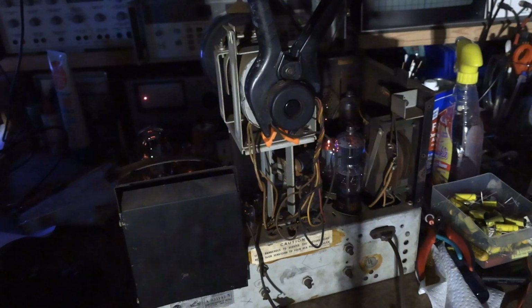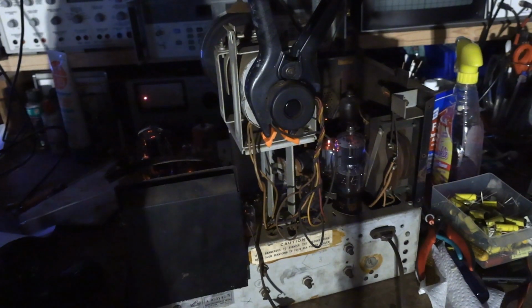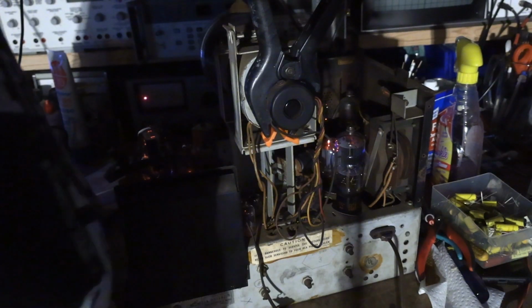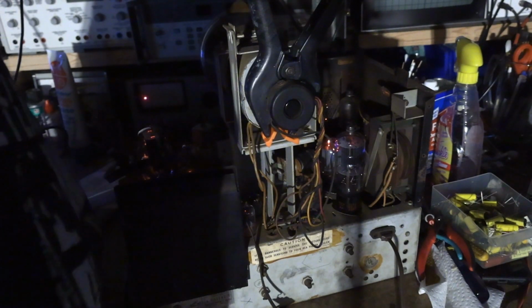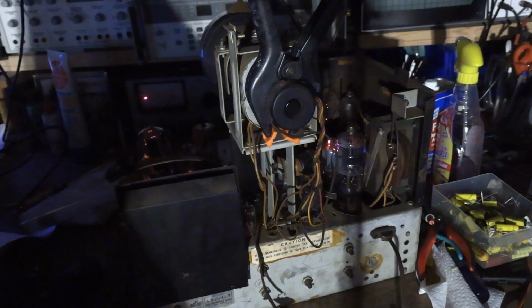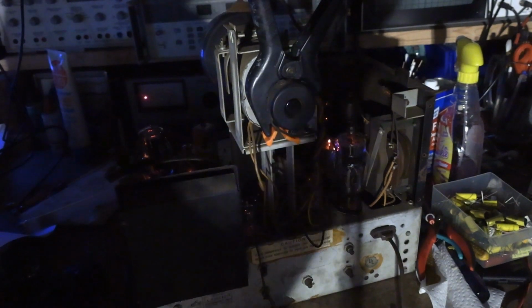Well, we certainly have had our share of bad high voltage rectifiers. Now I did test this one - it tested weak, but it's not dead. I see the filament on it glowing now. Well, let's get our high voltage probe and see what's going on.